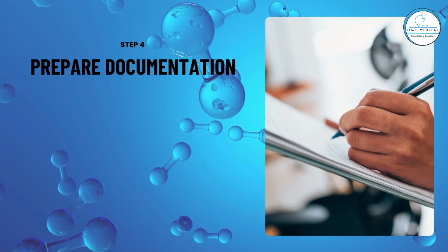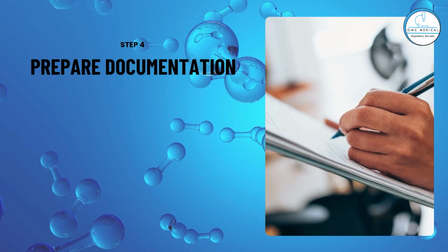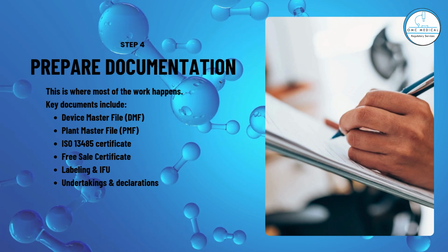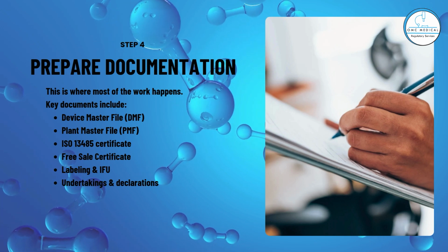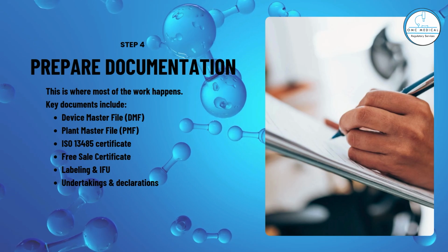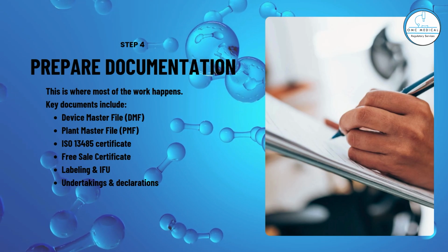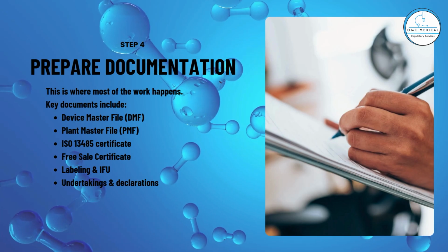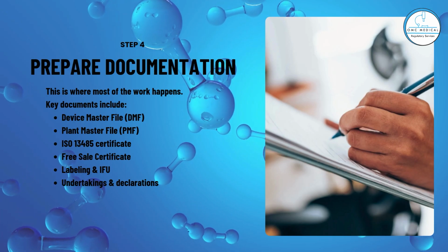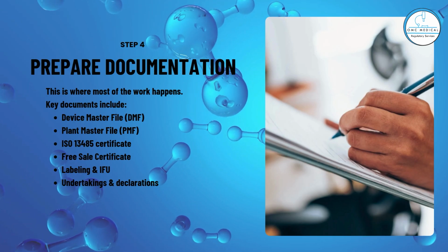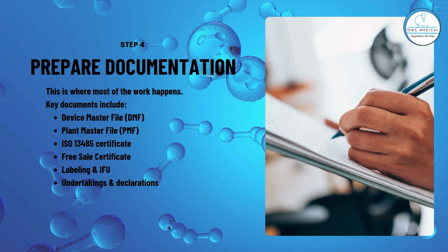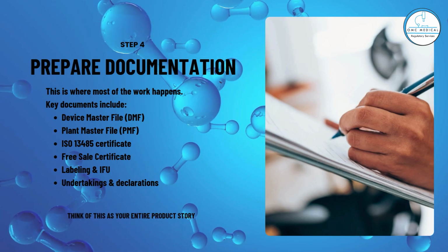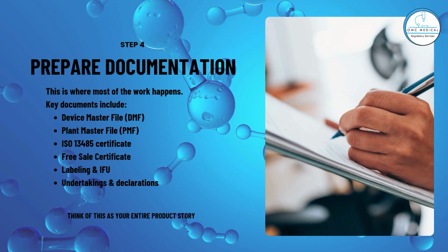Step 4. Prepare documentation. This is where most of the work happens. Key documents include Device Master File, DMF, Plant Master File, PMF, ISO 13485 certificate, Free Sale certificate, labeling and IFU, undertakings and declarations. Think of this as your entire product story.